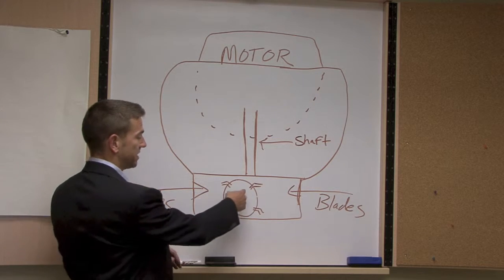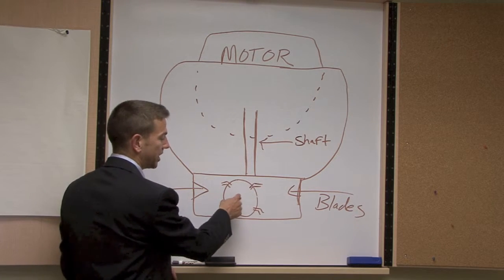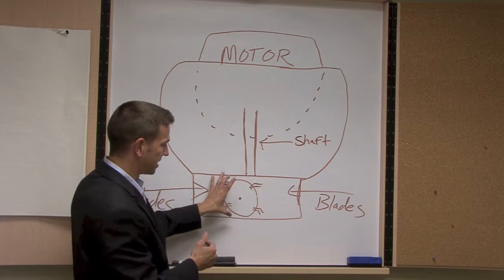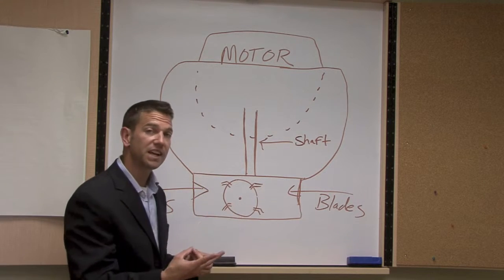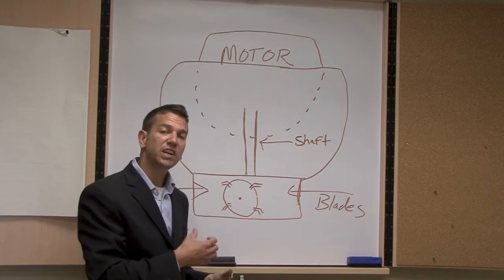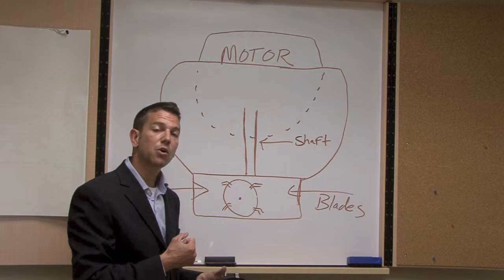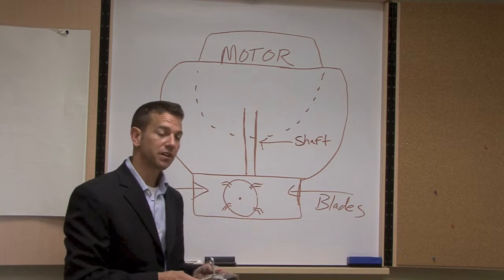So what we do is we take a four inch hole cutter, we cut a hole right into that spot, that vertical piece of aluminum, two if necessary, and then we go ahead and we reach our arm in there and we can use a scraper or we can use our gun, our power washing gun to make sure we get all the grease off of there.